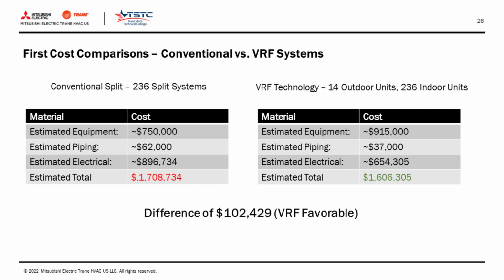Now, by comparison, on the VRF side, only the 14 outdoor units require home runs, as it is the branch circuit controllers which use a home run, not each individual apartment. And looking to the electrical cost, this project was modeled against these seemingly inexpensive split units with roof-mounted condensers for AC and electric heat for heating. Well, those electric heaters require 15 kW of electricity, and depending on line length, that 15 kW is going to require 40 or 60 amp breakers, along with number 4 or number 6 wire size. Again, that's a lot of copper.